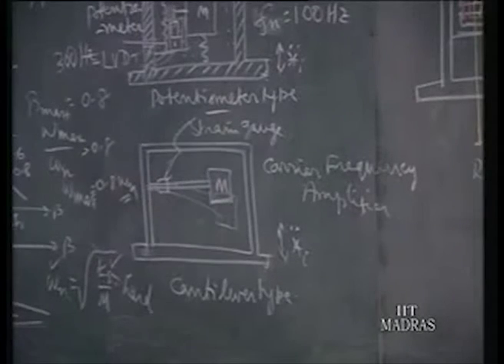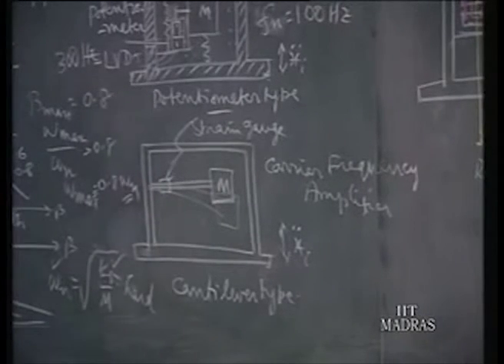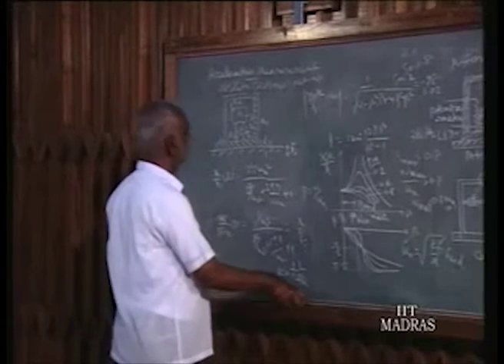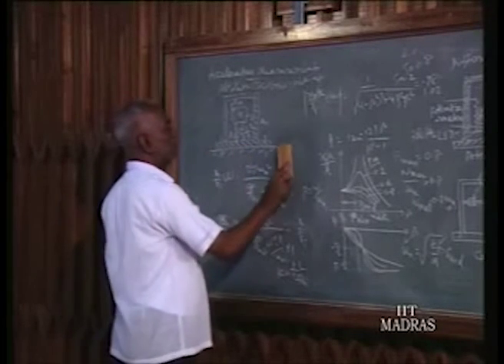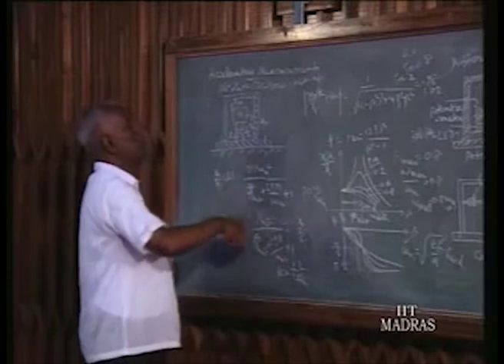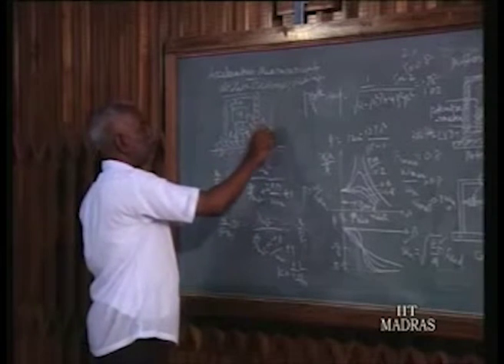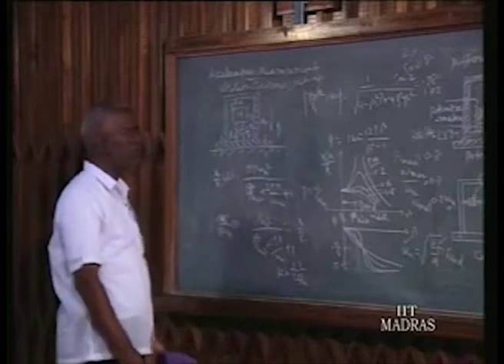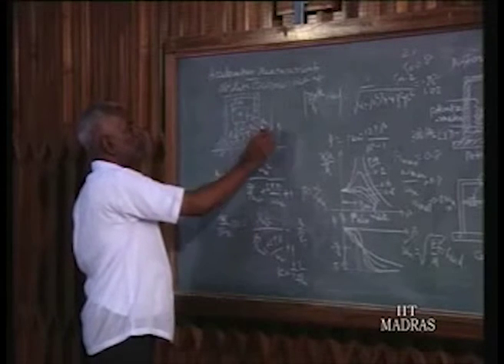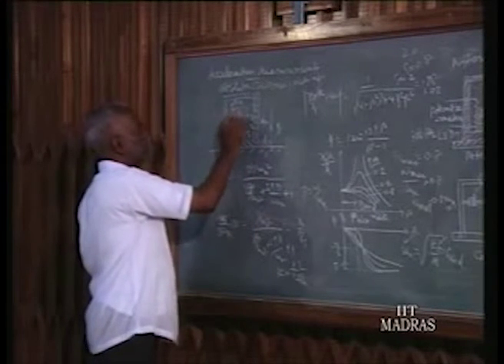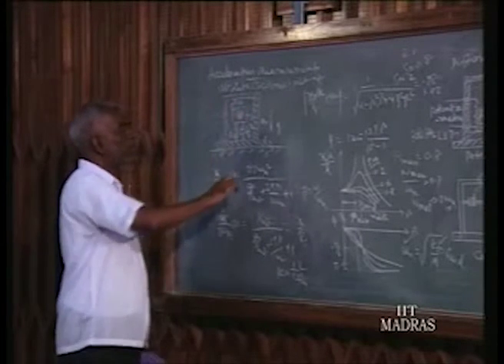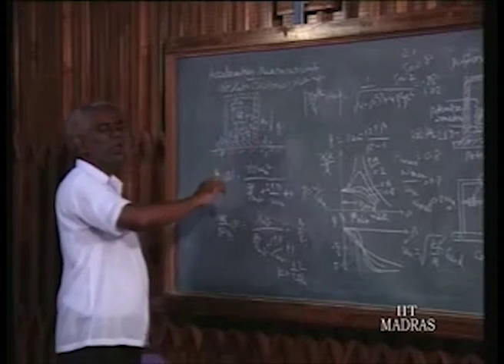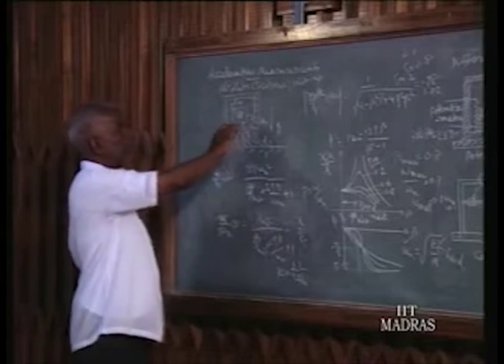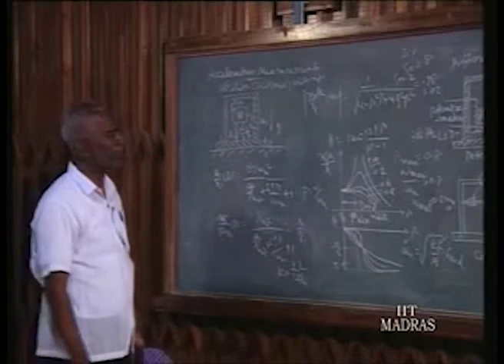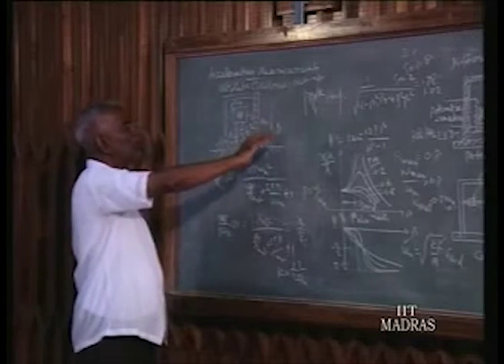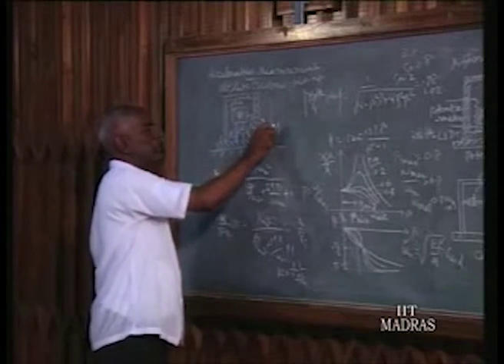How is it calibrated? Suppose when you want to calibrate, suppose this is the basic instrument, we put it on the table, and then you will find G will be acting. G is the acceleration due to gravity. So due to G, the mass is converted in terms of weight. This weight acts over the spring and it deforms a distance, and that distance is measured by this relative displacement pickup, and that reading of the instrument we write as plus G.